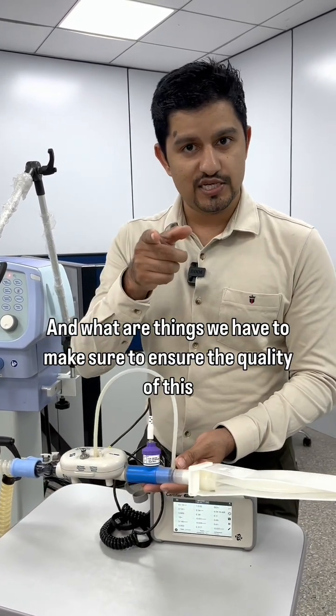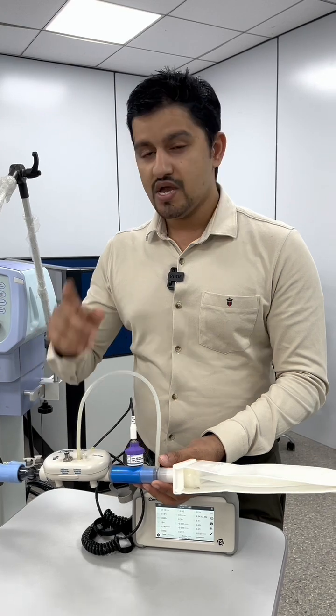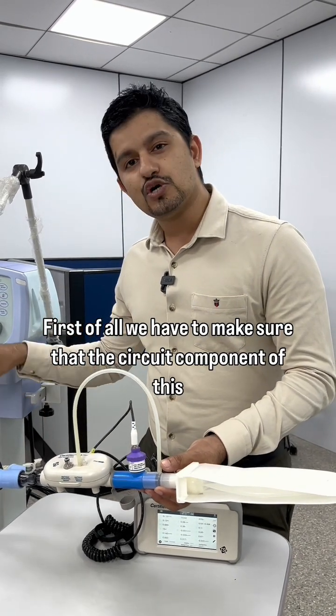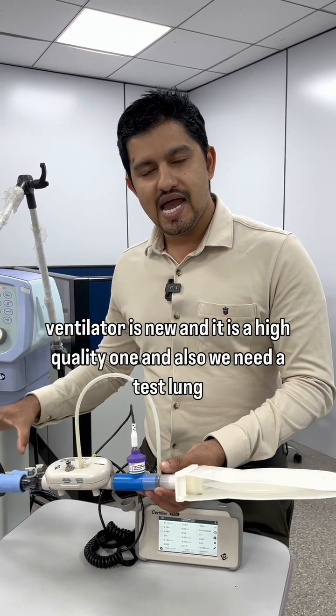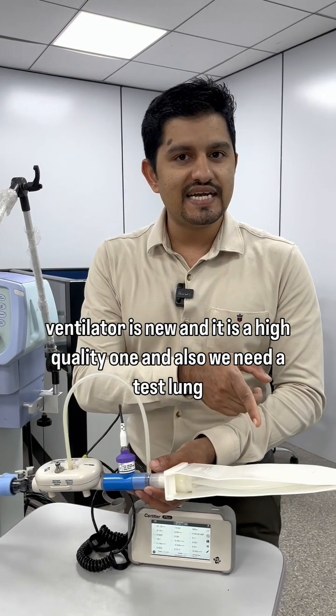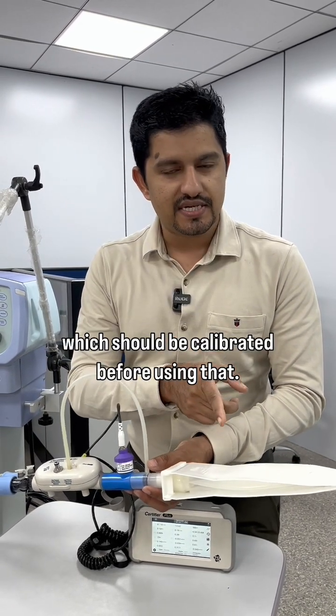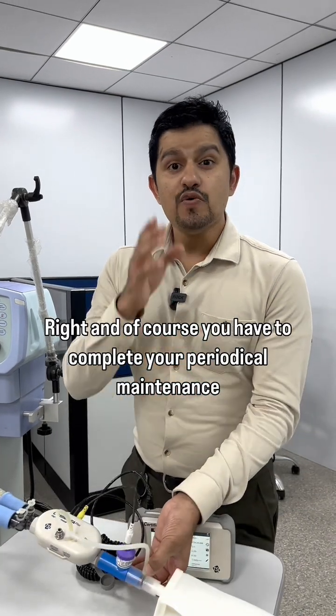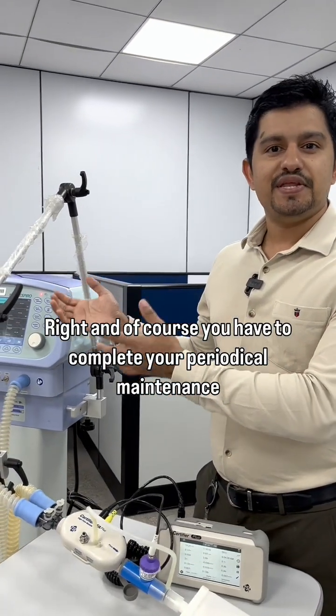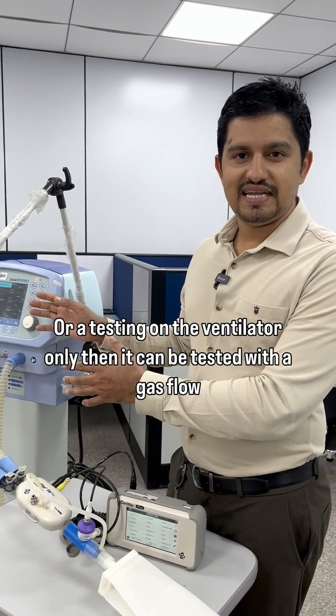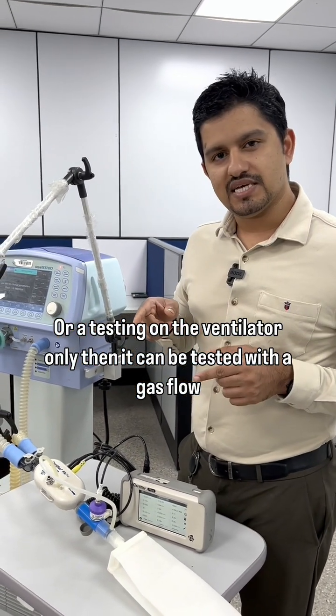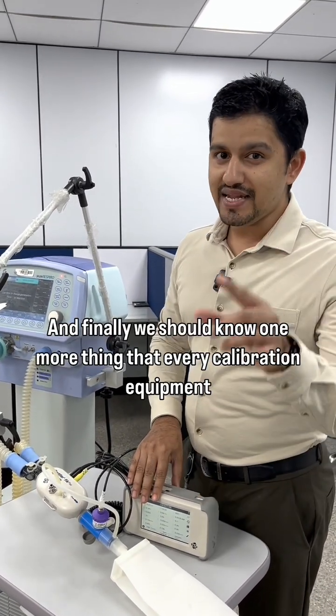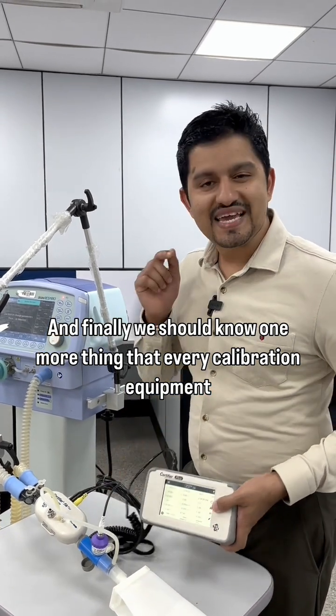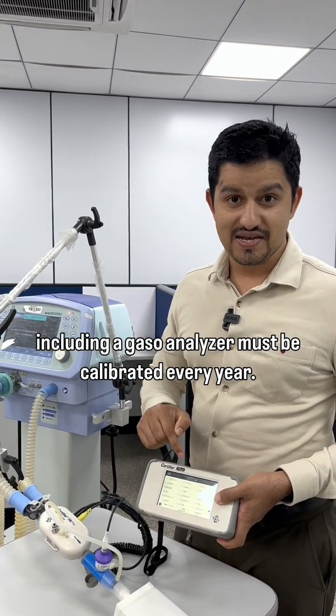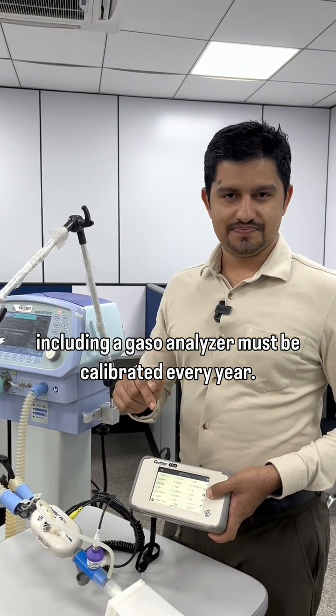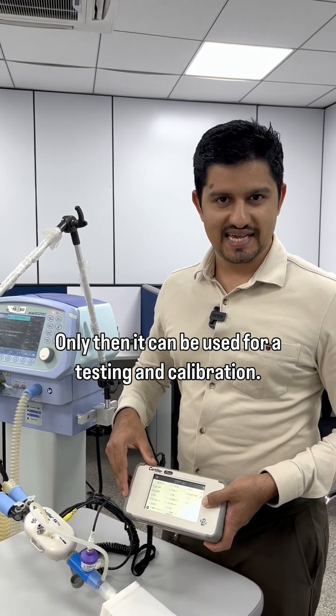What are the things we have to make sure of to ensure the quality of this testing? First of all, we have to make sure that the circuit components of the ventilator are new and of high quality. We also need a test lung which should be calibrated before use. And of course, you have to complete the periodic maintenance or testing on the ventilator. Only then can it be tested with the gas flow analyzer. Finally, you should know one more thing: every calibration equipment, including a gas flow analyzer, must be calibrated every year. Only then can it be used for testing and calibration.